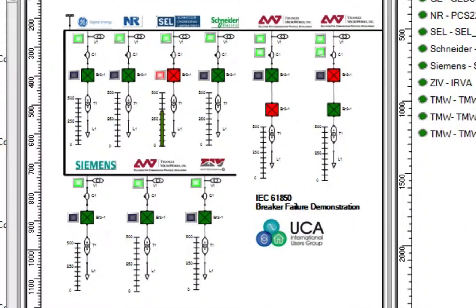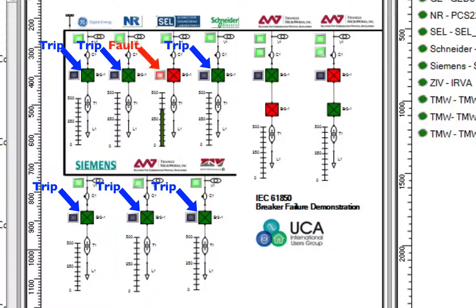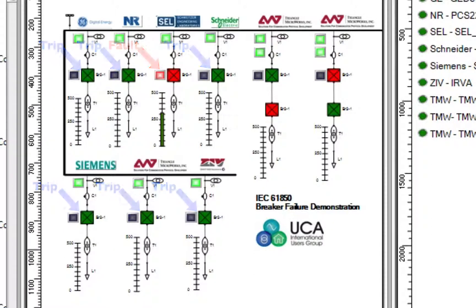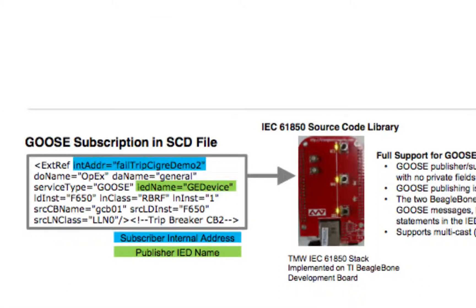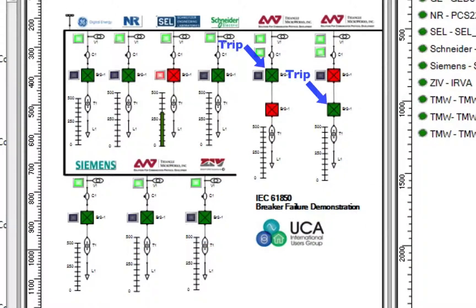Looking at the single line diagram, which shows the IEC-61850 data received by the client, we see that it is updated to show that each of the simulated breakers has tripped, except for the Schweitzer relay, which is showing a fault. Remember that the two BeagleBone boards in this demo subscribe to the same RBRF.opEx Goose messages, but use different intAddr assignments in the ExtRef statements in the IED section of the SCD file to trip different breakers. As expected, the single line diagram shows that one breaker on each BeagleBone has tripped, and that they tripped different breakers.